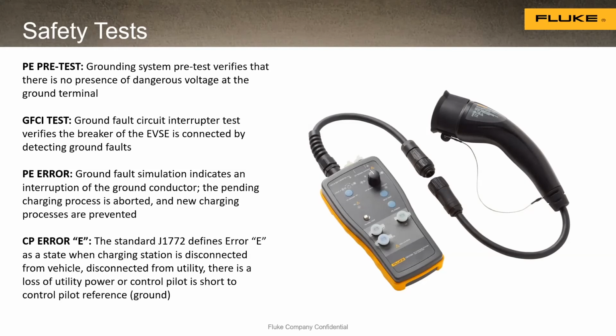When the system's working correctly, there are GFCIs built in. We can do a ground fault check, which trips out the charging station for a moment and brings it back online, confirming the internals work correctly. We can also do a ground fault simulation to see what the unit does if there was an actual ground fault. All of these are pre-checks to make sure it was installed correctly and the charging station is working correctly.